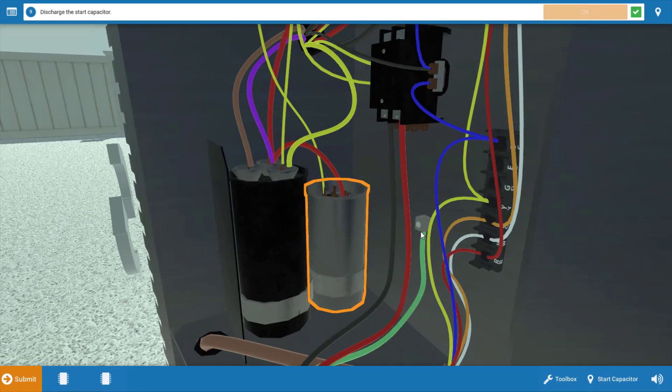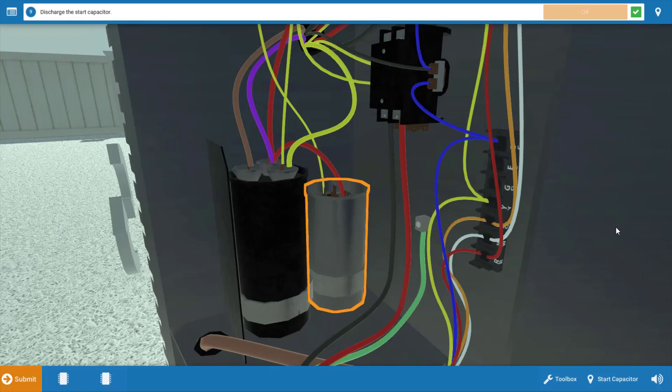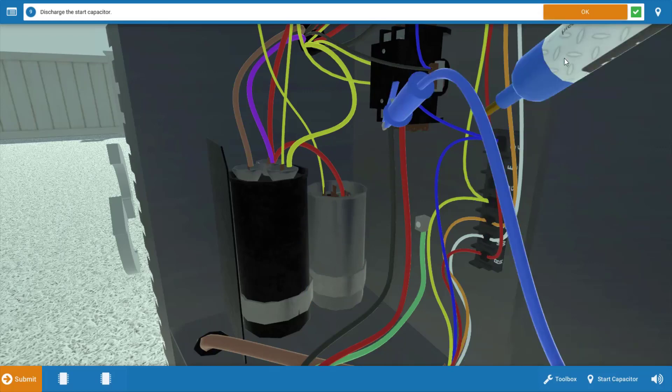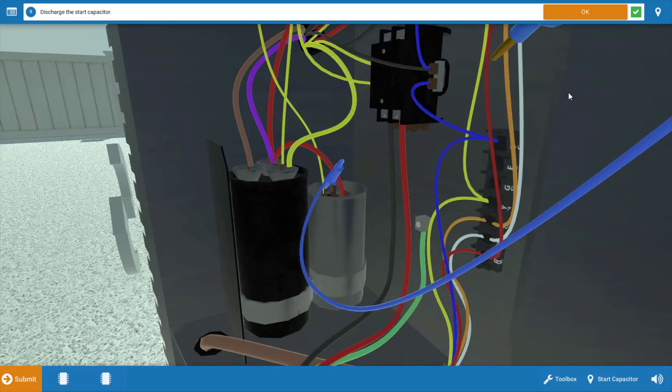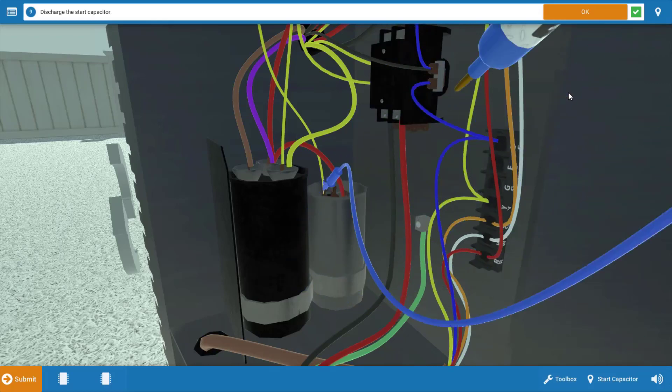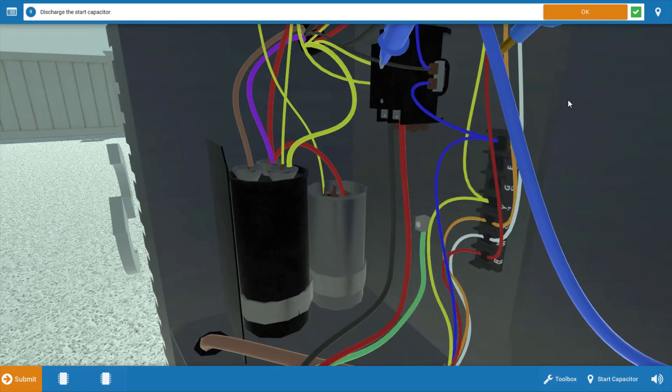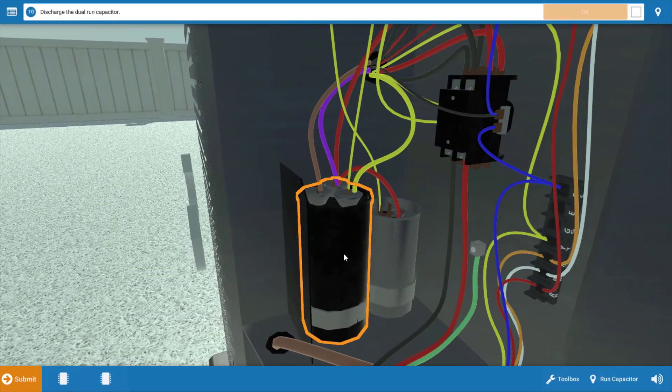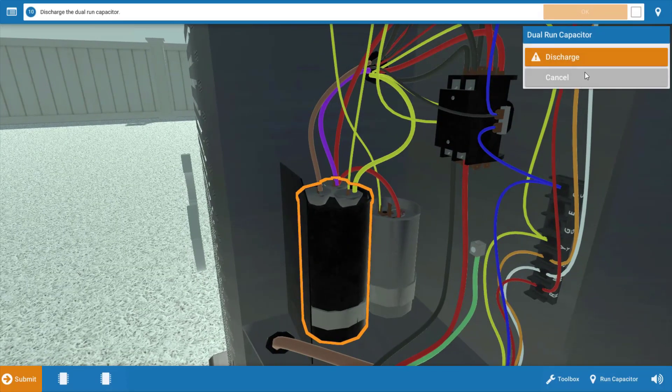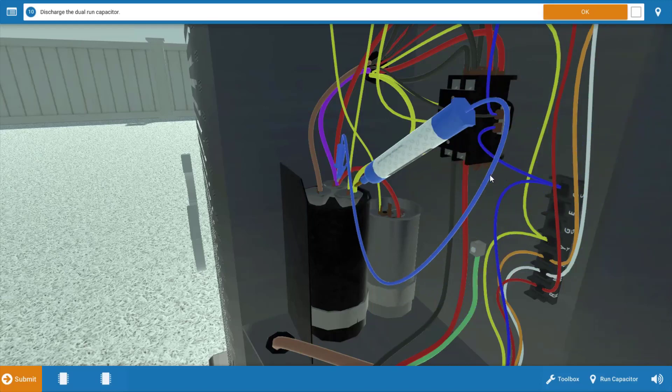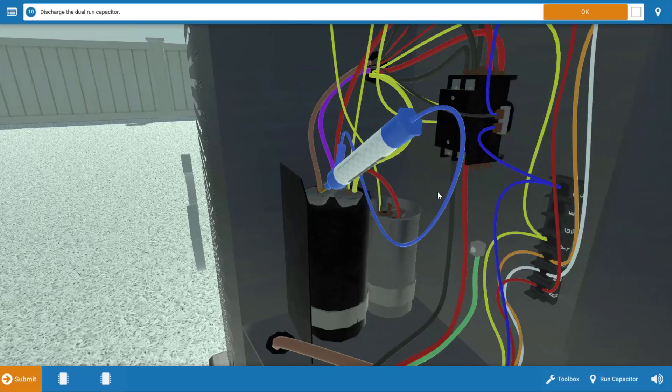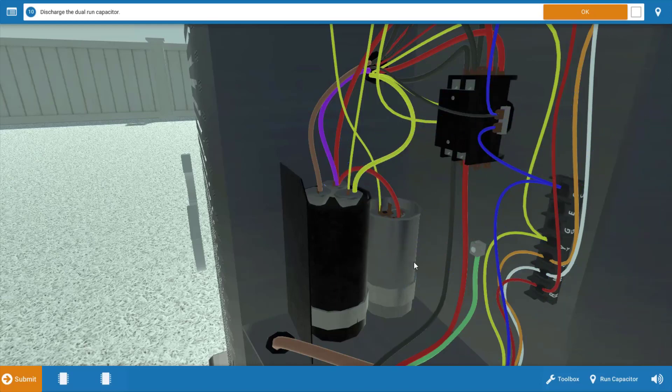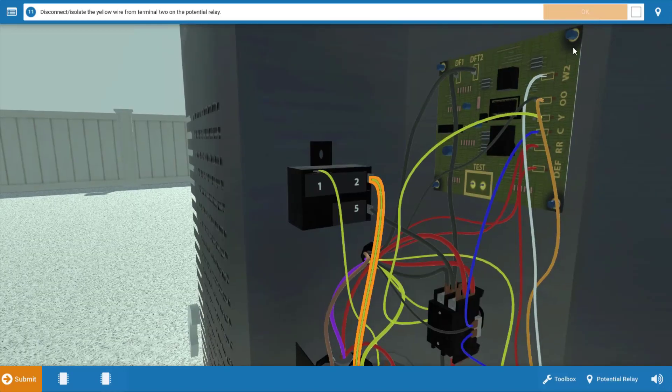Next, at the control panel, it's going to be necessary to discharge both capacitors. We're going to be working in a fully connected circuit, meaning these capacitors are connected to the potential relay as well as the motor. So simply click on the capacitor and discharge the start capacitor first. And this is a convenient capacitor discharge tool that's on the market. It's very inexpensive. I don't suggest using a screwdriver. That could potentially damage the capacitor. After you've discharged the start capacitor, click OK. And next, we're going to discharge the run capacitor. And again, once the capacitor is discharged, it's safe to work on this circuit now. And remember, the power's off, but the capacitors could potentially hold a charge once the power is de-energized. So once we've discharged the run capacitor, click OK.